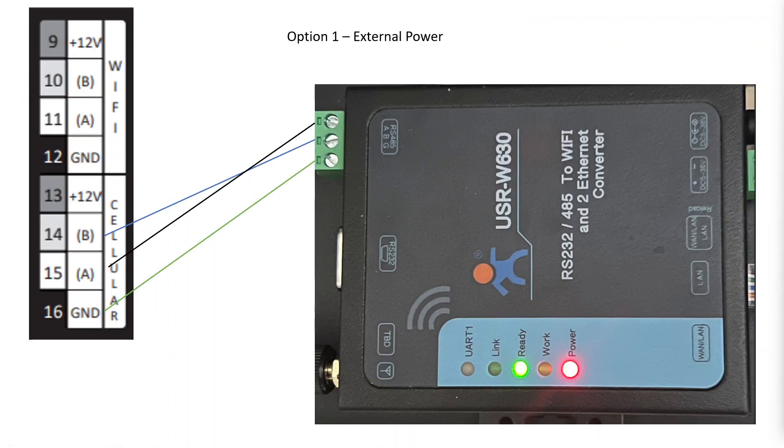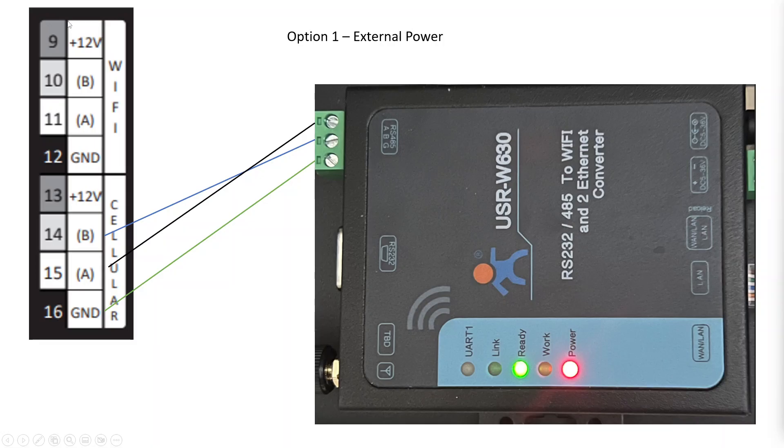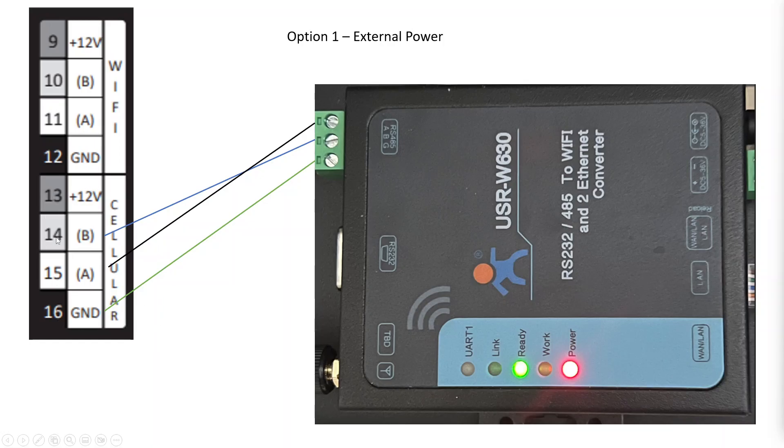You have a couple options on how to set all of these up. This is showing the converter device, but this applies to the Raspberry Pi to a large extent as well. The icon on the left is the terminal bus that is on the generator itself. You connect to the cellular side of the device. The Wi-Fi side, even though it looks the same and has the same letters and numbers on it, does not output the same data. So you need to connect to the cellular side of the terminal block.